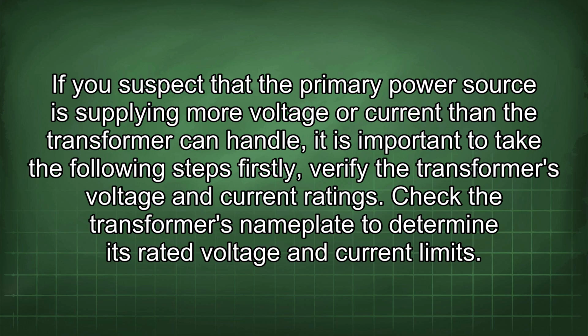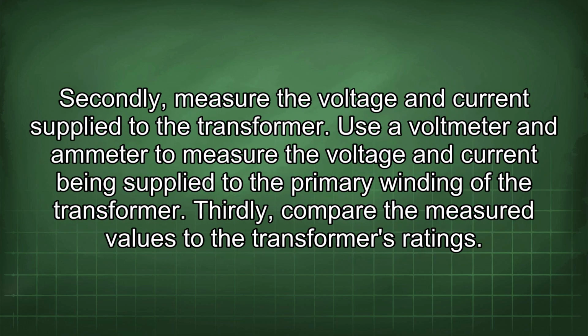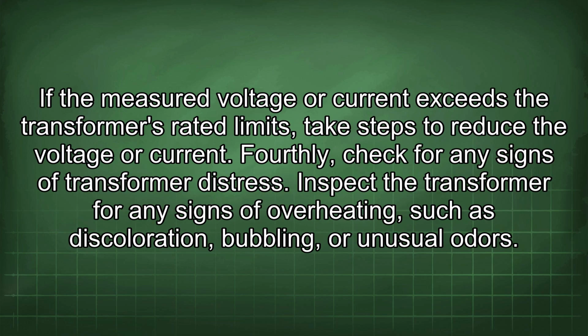Firstly, verify the transformer's voltage and current ratings. Check the transformer's nameplate to determine its rated voltage and current limits. Secondly, measure the voltage and current supplied to the transformer. Use a voltmeter and ammeter to measure the voltage and current being supplied to the primary winding of the transformer. Thirdly, compare the measured values to the transformer's ratings. If the measured voltage or current exceeds the transformer's rated limits, take steps to reduce the voltage or current.